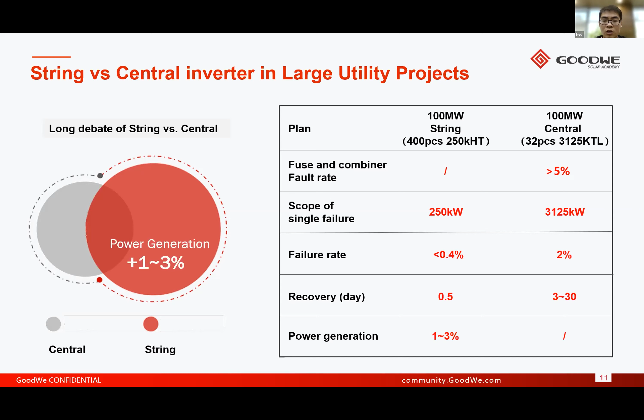Firstly, a central inverter needs an external combiner box, which can cause a failure rate of more than 5% over the lifetime. If a fuse melts, you need to find it and replace it. That may take a lot of work. String inverters won't need the combiners. Besides, we can always keep 1 or 2 spares depending on the capacity in the case of string inverters. We can change them when needed. The redundancy improves and the downtime will be less. So considering the multiple MPPT feature, recovery time, and generation, we assume a string inverter may have 1 to 3% power gain compared to central over the lifetime.